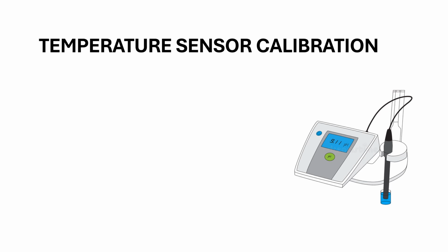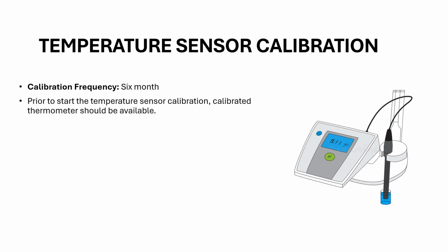Here we will discuss the temperature sensor calibration. Let's start with calibration frequency. The temperature sensor calibration should be performed every 6 months to ensure accurate measurement, right? Before beginning the temperature sensor calibration, make sure a calibrated thermometer is available. This thermometer will serve as a reference to verify the accuracy of the temperature sensor.